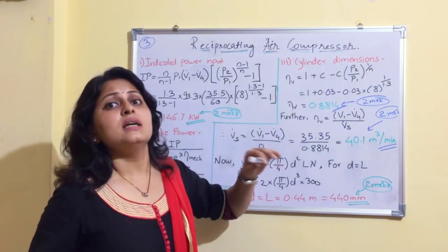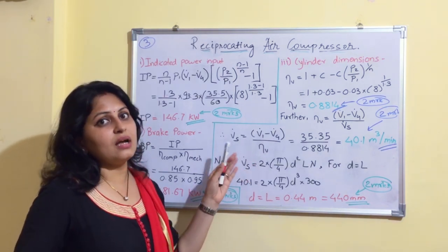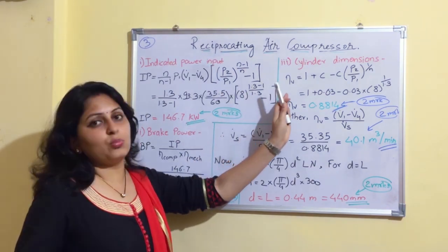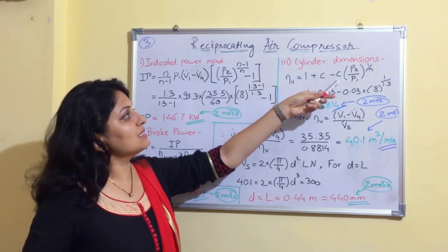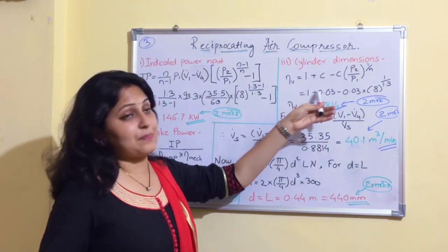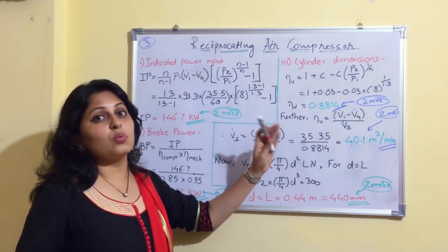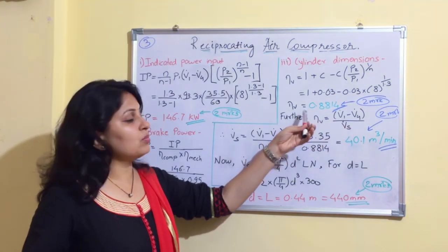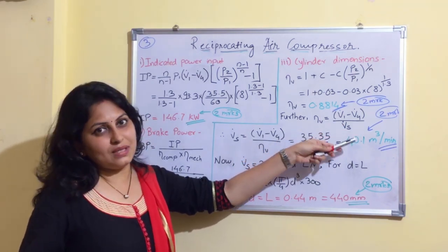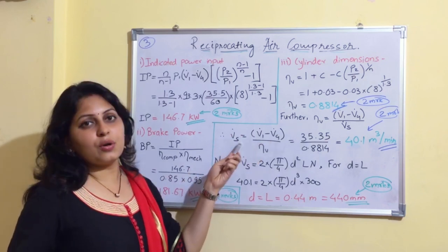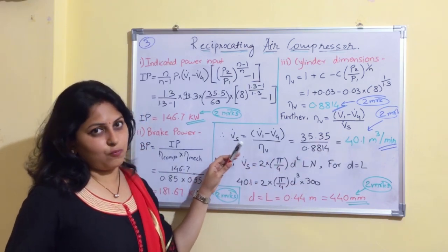The next term is cylinder dimensions — diameter and stroke length. To find these, we first calculate volumetric efficiency using η_vol = 1 + C − C·(P2/P1)^(1/n). Substituting all values, we get η_vol = 0.8814. Then using η_vol = (V1−V4)/Vs, we get swept volume Vs = (V1−V4) / η_vol = 40.1 m³/min.